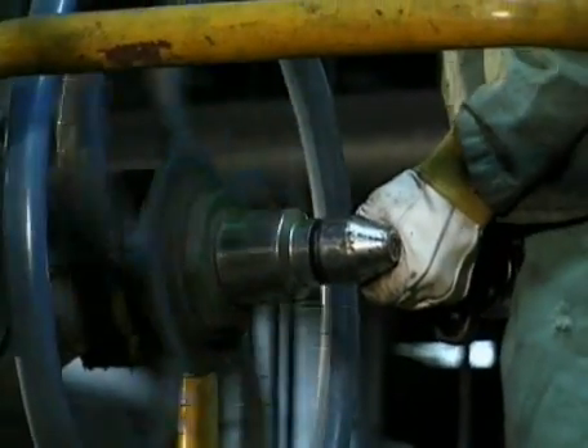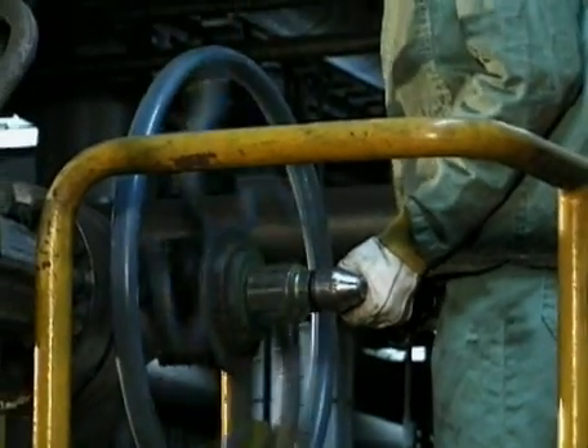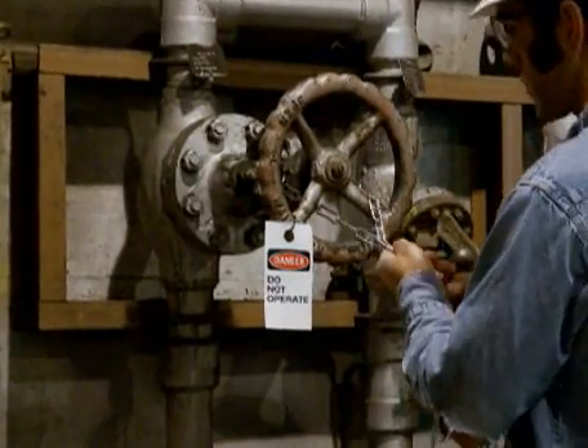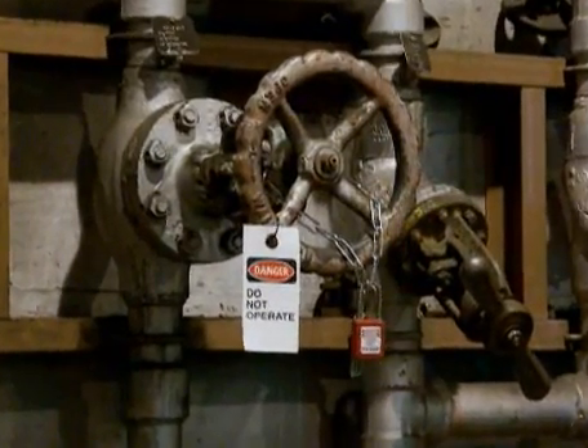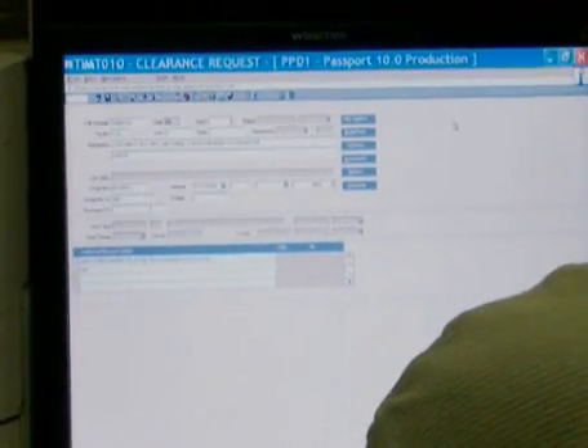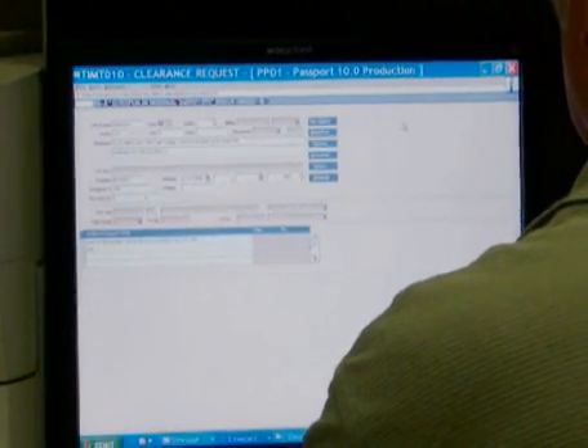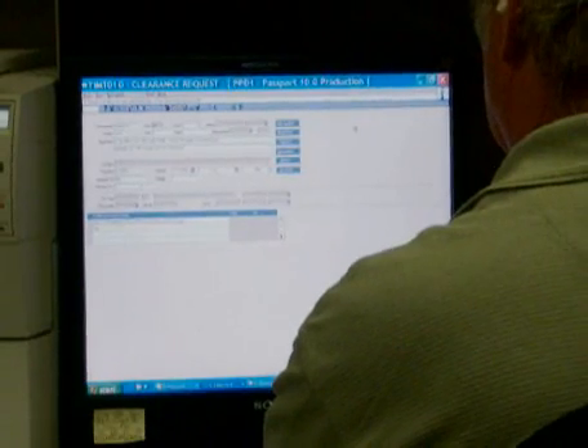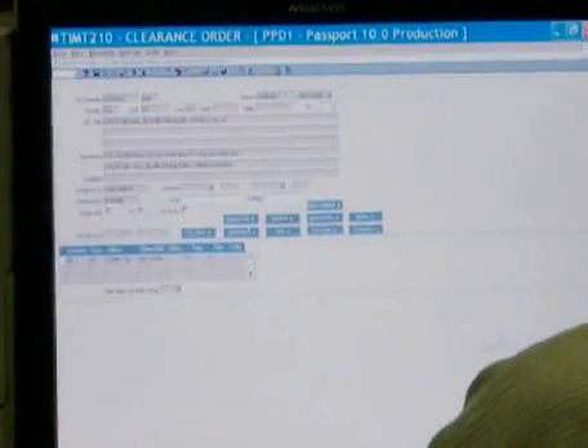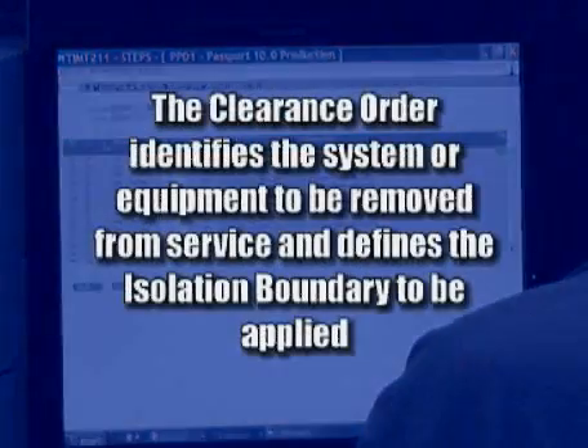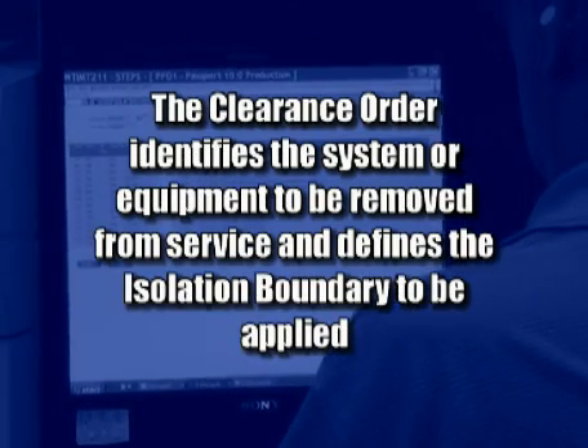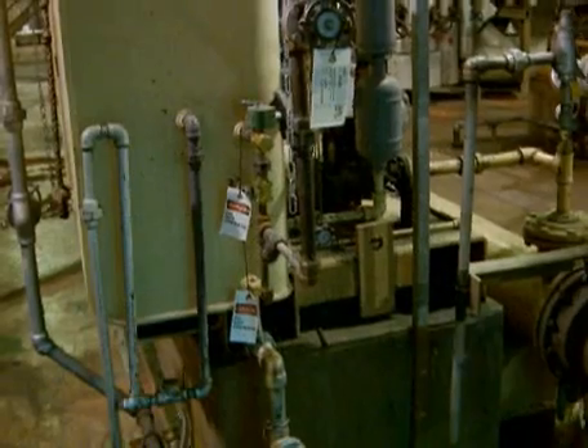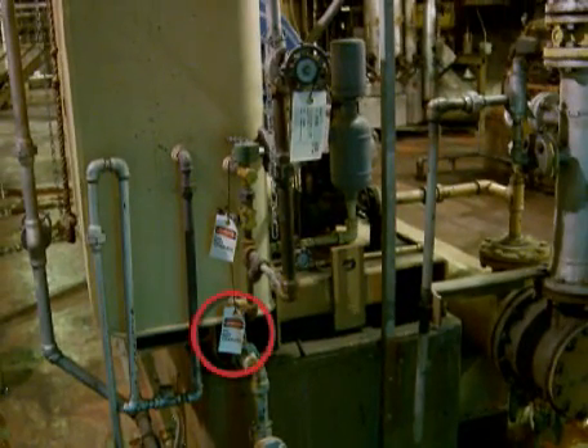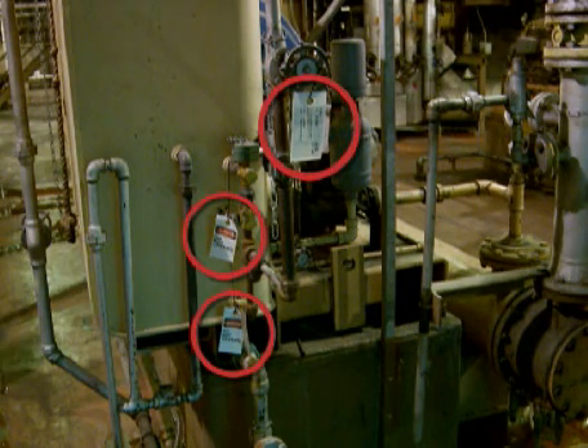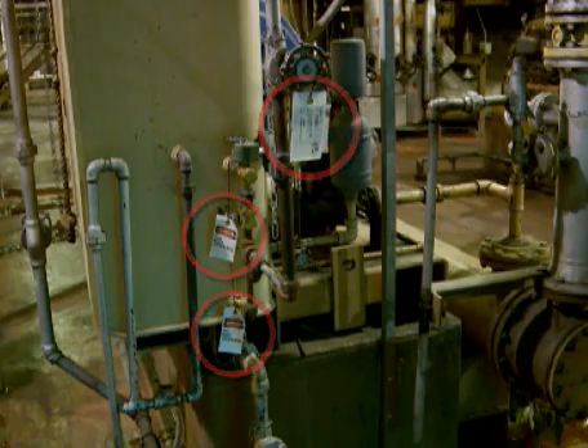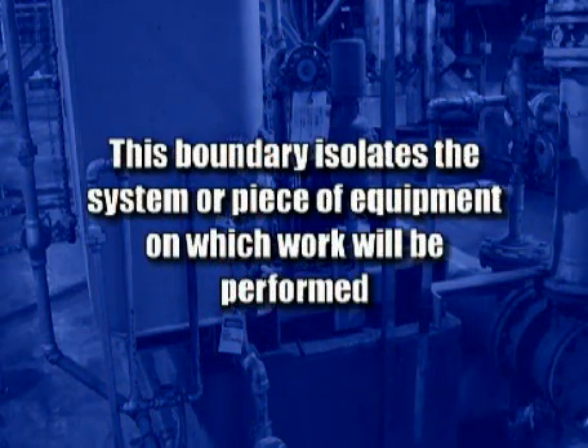While performing your work, it may be necessary to remove or shut down a system or piece of equipment for maintenance. Should this occur, it is important that PPL's energy control process be followed. The first step in this process is an electronic clearance request made by one of PPL's authorized personnel, such as an engineer, planner, supervisor, or mechanic. A clearance order is then electronically generated. The clearance order identifies the system or equipment to be removed from service and defines the isolation boundary to be applied. An isolation boundary can be comprised of one or more energy isolating devices, EIDs, that are positioned to restrict the passage of energy into a work area. This boundary isolates the system or piece of equipment on which work will be performed.